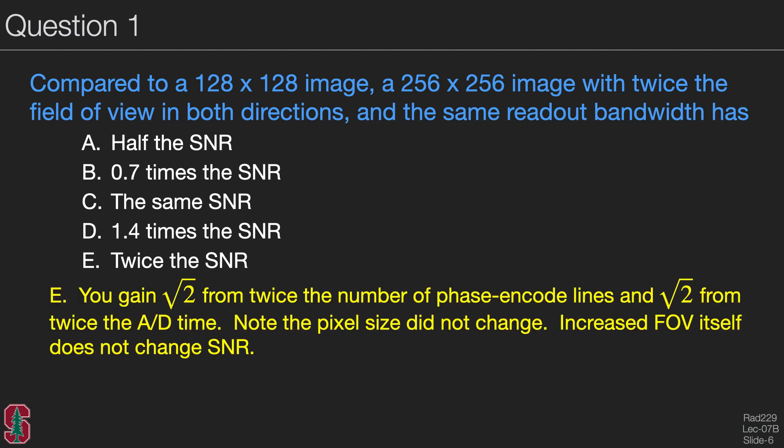Compared to a 128 by 128 image, a 256 by 256 image with twice the field of view in both directions and the same readout bandwidth has which SNR relationship? The answer is E: you gain a square root of 2 because you have twice the number of phase encoding lines, and an additional square root of 2 because you have doubled the A-to-D time. Both factors give a square root of 2, so overall you get twice the SNR. Notice that the pixel size did not change, and increasing the field of view itself does not change the SNR.